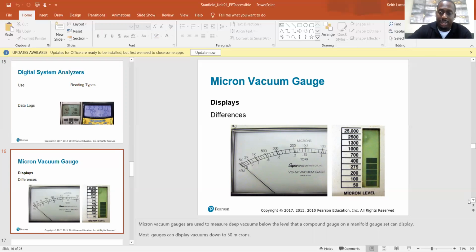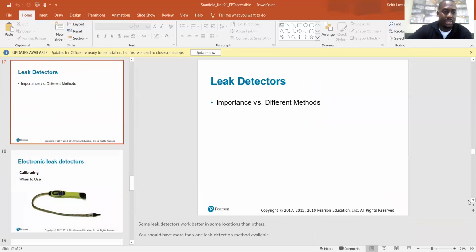which is crazy. 500 is the target. If you get below 500, you're just in good shape. I did an install this weekend, and it's a brand new install, so the recovery is usually not a factor. The evacuations usually go pretty good on a brand new system. Plus it doesn't even include the condenser because we don't even open the valves on the condenser until the evacuation is complete. So with that being the case, usually on a brand new install, the evacuation goes pretty quick. And in this case, it did. It was already at 500 before I was even ready to start it up.